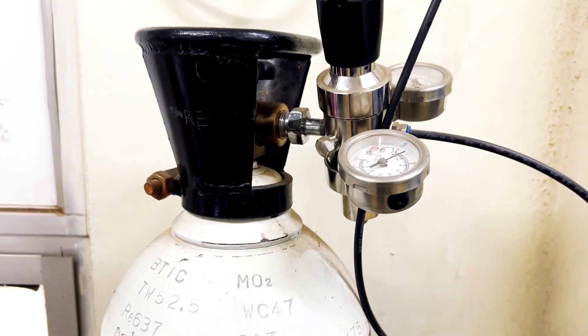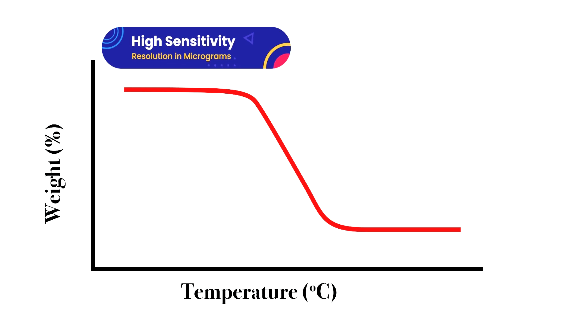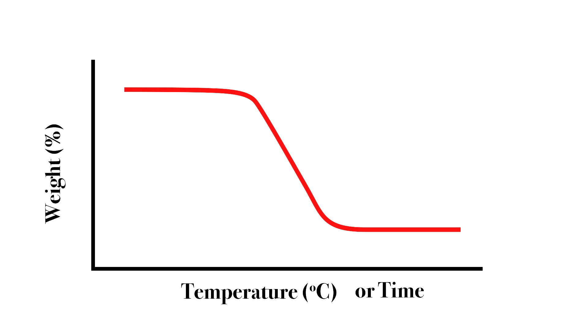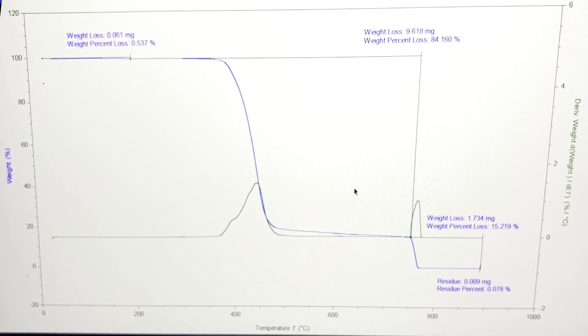The TGA also has a provision for controlled gas delivery where we can choose either oxygen, nitrogen, air, or any other specific gas that is used for control studies. And finally, no system is complete without the software. In this case, the software records the weight, which is in the order of micrograms, as a function of temperature as well as time. The software is also capable of displaying the results in the form of graphs for easy visualization.